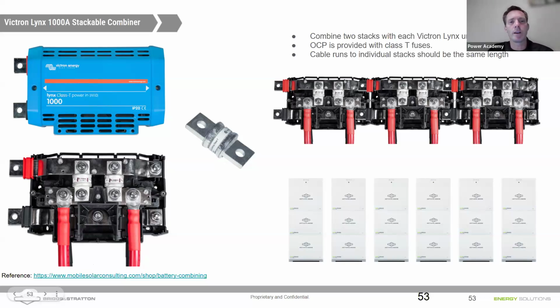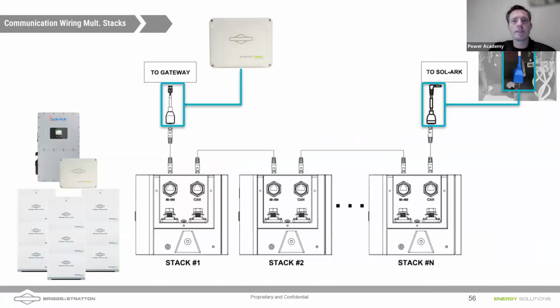And these come in much cheaper than the Midnight combiners. In fact, a single one of these units you can get for under $170, and the fuses themselves are quite cheap as well. So if you're doing 6 stacks of batteries, you can stack these Class T power ins. They're 1000 amp combiner bus bars. They're quite heavy units, nicely made. And so this is a nice option for doing 3, 4, 5 or 6 stacks of batteries, right? With individual overcurrent protection, easily done.